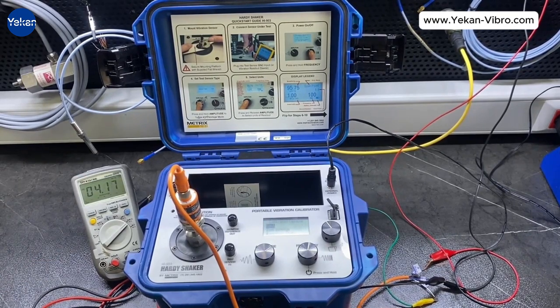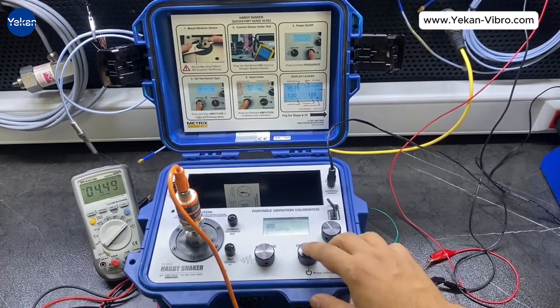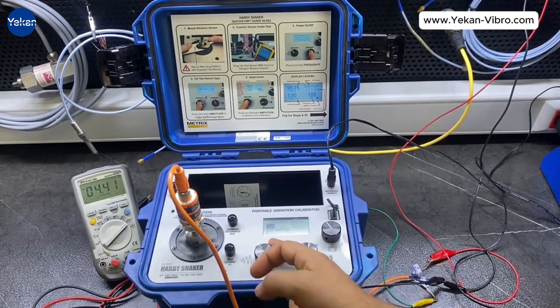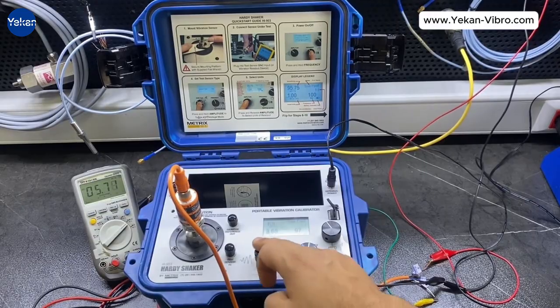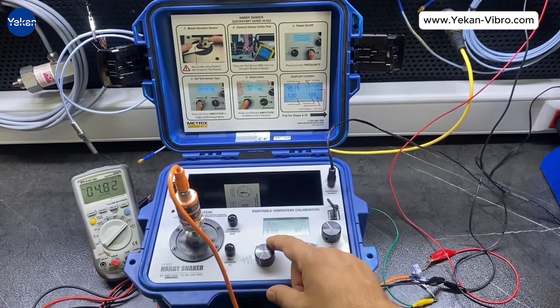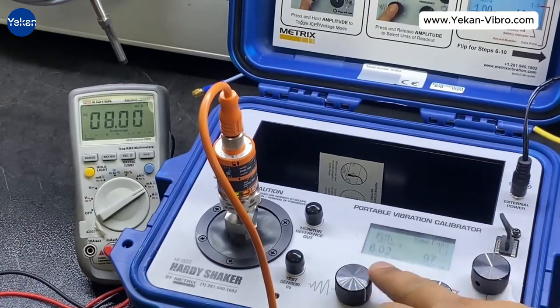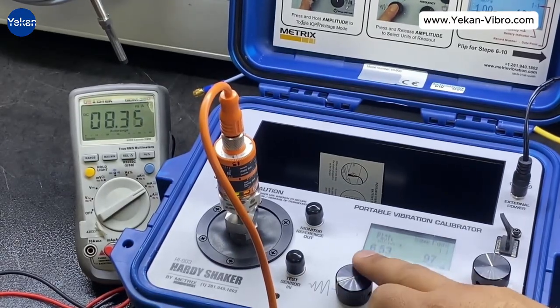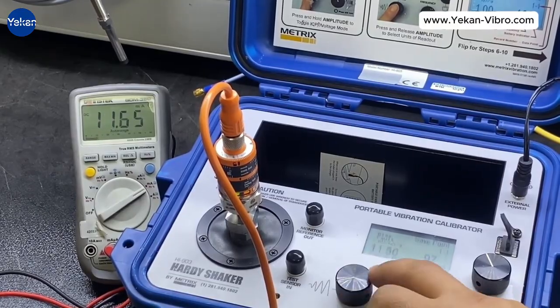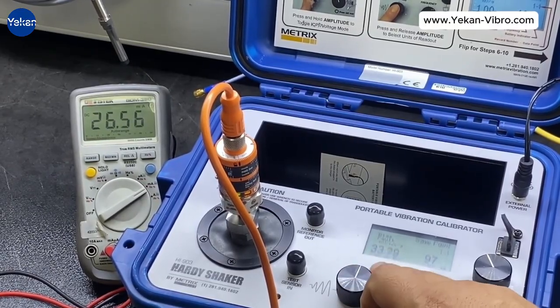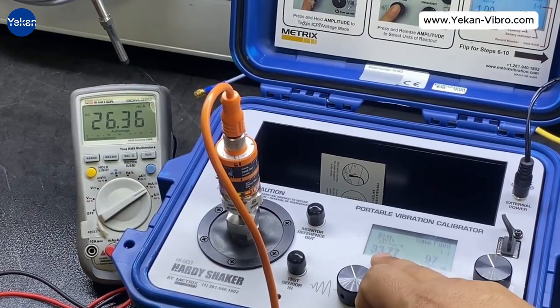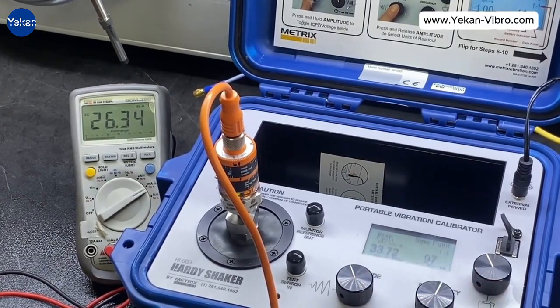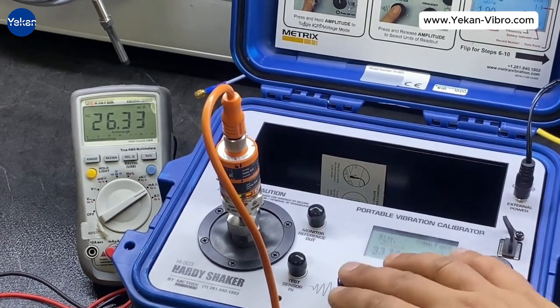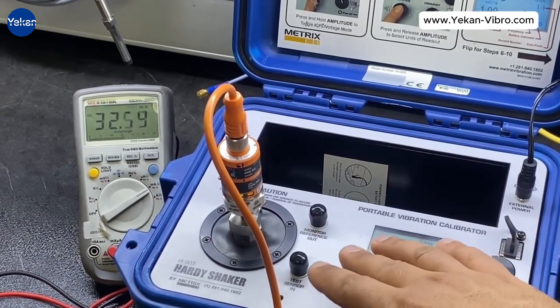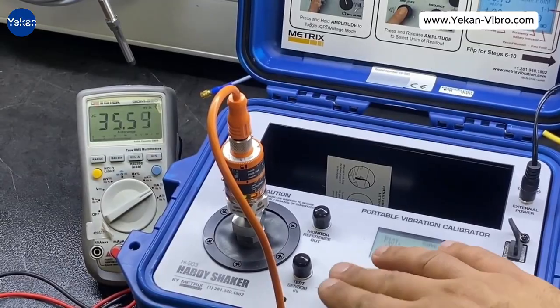Now I apply light foot taps to the floor and you see the reading goes up. That means the sensor is detecting vibration. I now turn on the shaker. First, I lower the amplitude to minimum, about 2 mm per second. As I increase amplitude, the sensor's output current also increases. Eventually, the amplitude reaches 33 mm per second, which exceeds the valid 4 to 20 milliamp range. At this point, the output becomes saturated. You can see the current goes up to 30 milliamps. This is not ideal.